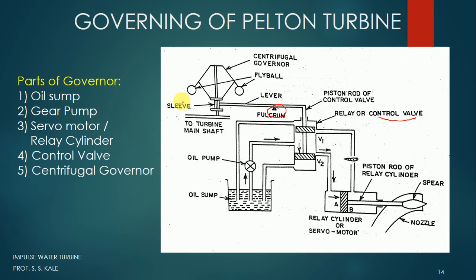Next is the centrifugal governor, which you may have seen in the theory of machines. It contains fly balls. When the rotation of the governor increases, the fly balls move up, and as the fly balls move up they take the sleeve along with them, so the sleeve also moves upward. This sleeve is connected to the lever, so when the sleeve moves upward the lever also moves upward. This centrifugal governor is connected to the turbine by a shaft, so if turbine rotation increases, the governor rotation also increases, and vice versa.